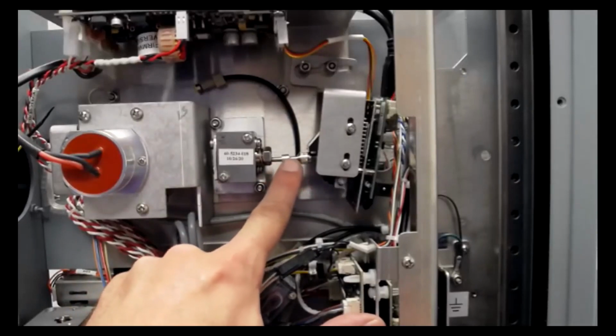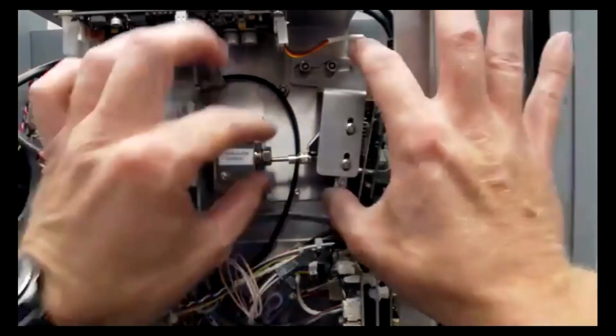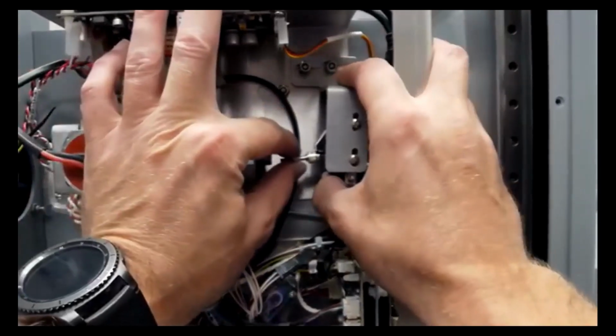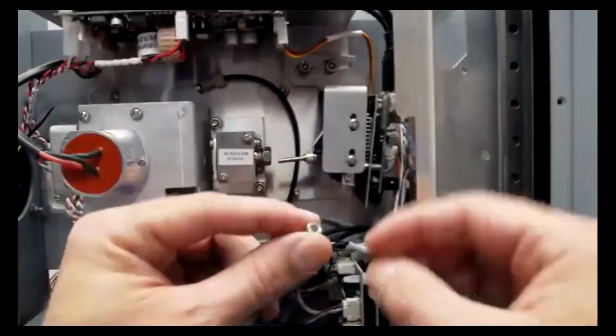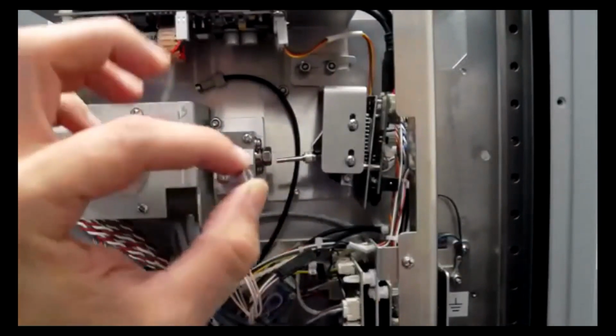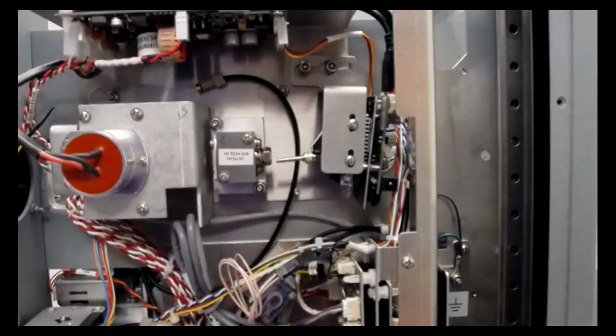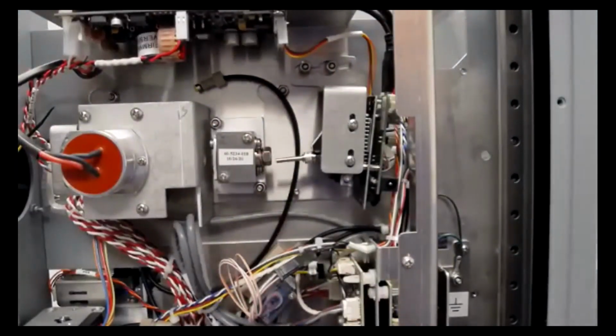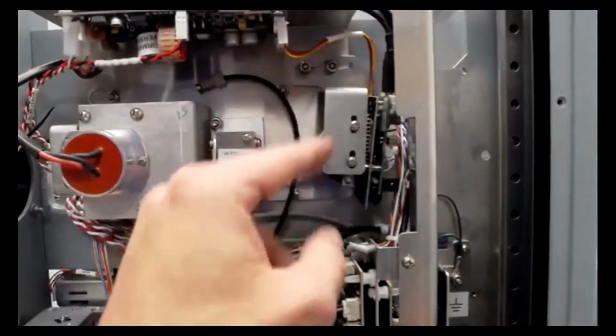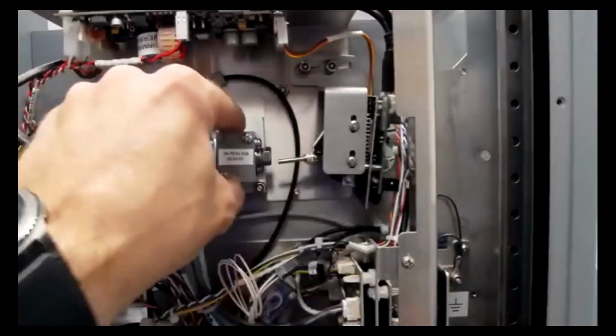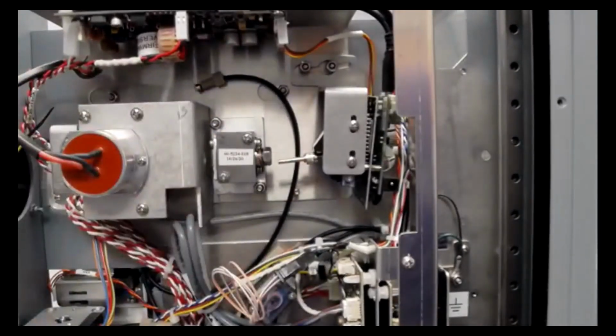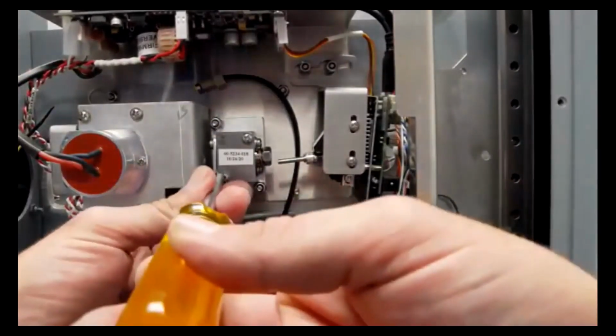So when you do this, what I do usually is I put my fingers on it and I just wiggle this so that I can take that spacer out and I set it aside for later. I don't want to lose that spacer. I'll explain why a little later. So I got that detector out of the way. I've got the tubings off the flow cell. All right, now it's time to take the flow cell out.